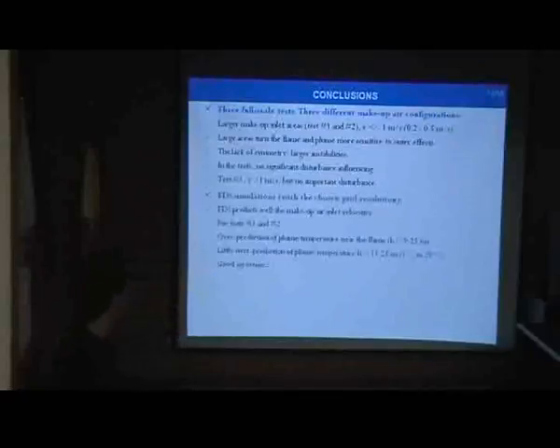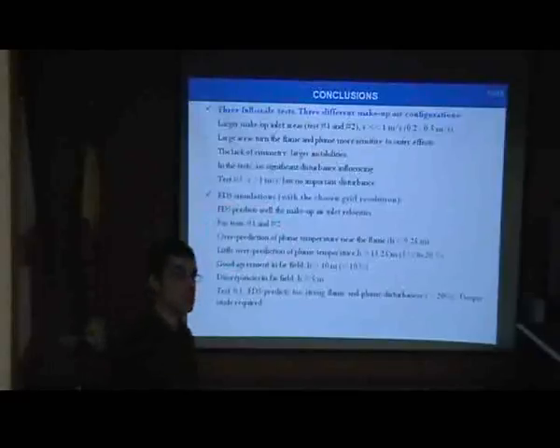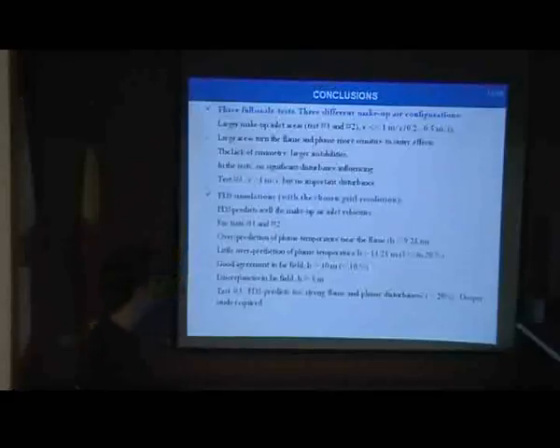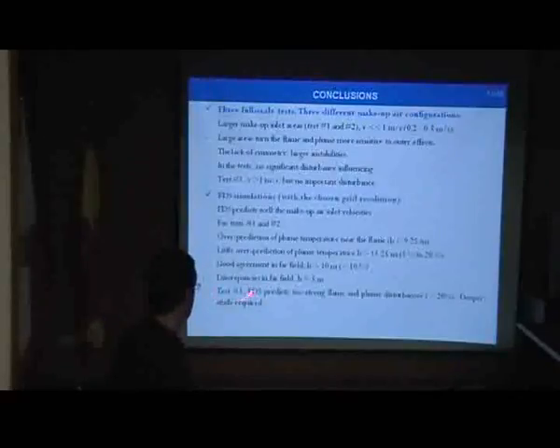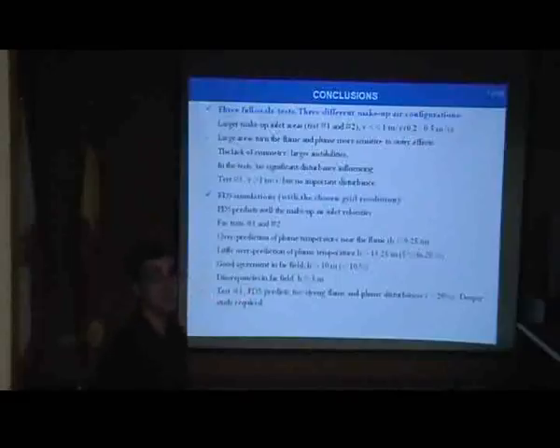Well, now, regarding the simulations with the resolution chosen, the make-up air velocities have been well-predicted for the three tests. However, if we take into account only the two first tests, the temperature at the upper part has been quite well-predicted, with more differences at the lower parts. But, regarding the third test, a non-physical solution is predicted by FDS, which predicts strong flame and plume disturbances.